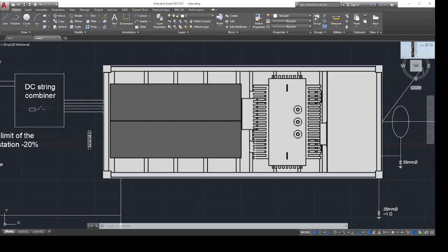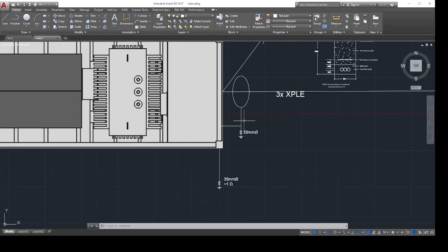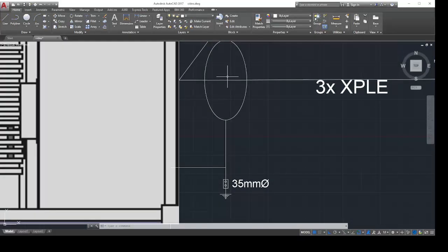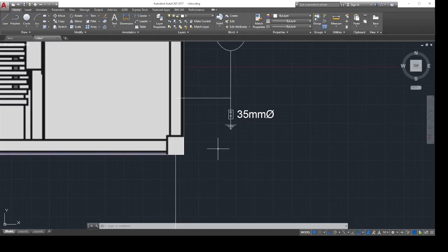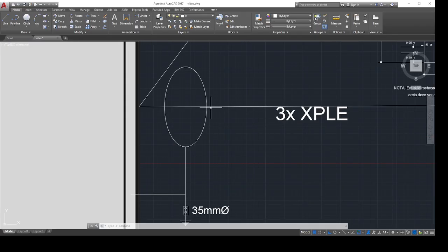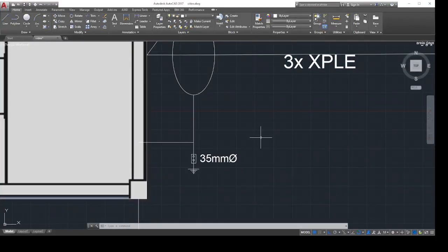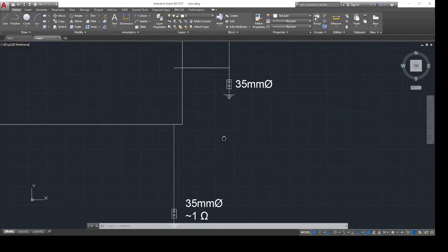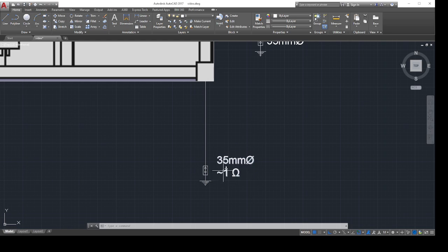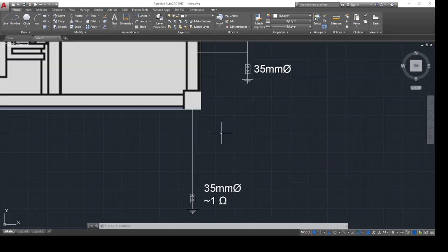The power station we already discussed. These cables are going to connect to one earth cable. This has to be measured, tested from the medium voltage side. It has to be tested with an isolation test, and the earth has to also be tested, to 1 ohm, more likely.